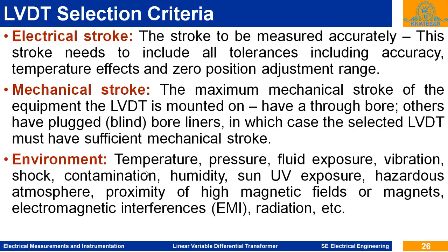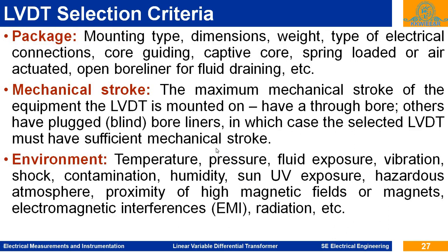Environmental condition, working condition: the environmental temperature, pressure, fluid exposure, vibration, shock, contamination, humidity, sun ultraviolet exposure, hazardous atmosphere, proximity of high magnetic fields or magnets, electromagnetic interference, radiation. What kind of environment are you going to use this LVDT in? You must specify that while selecting the LVDT.